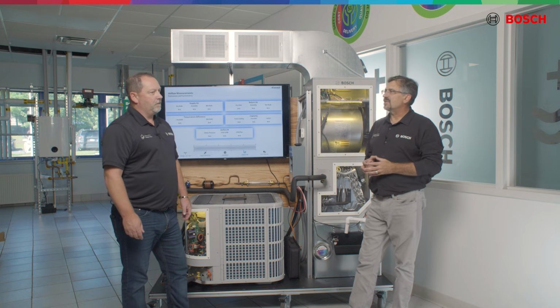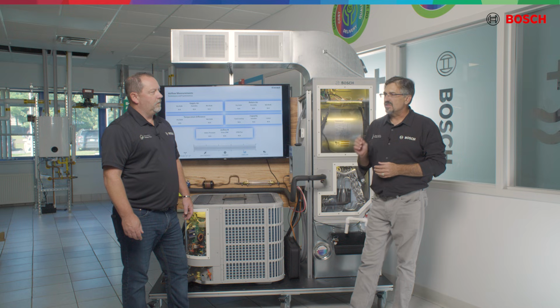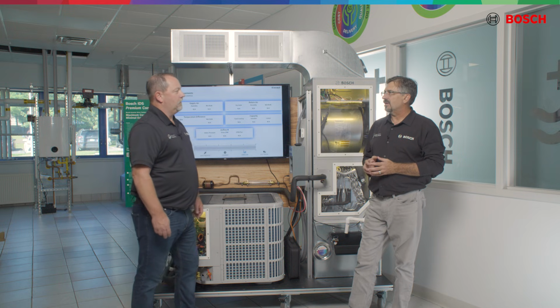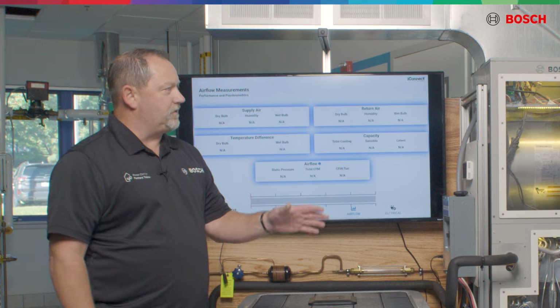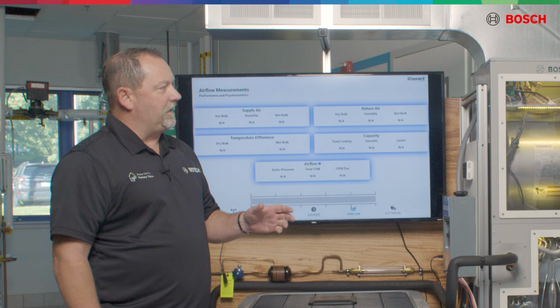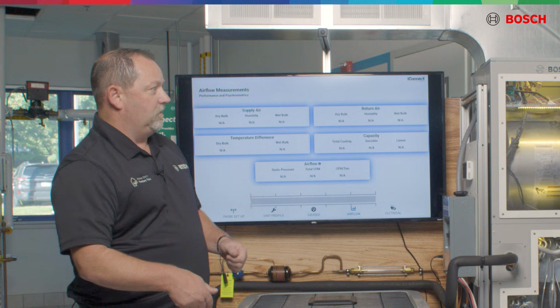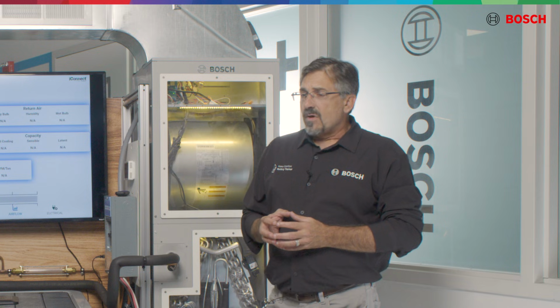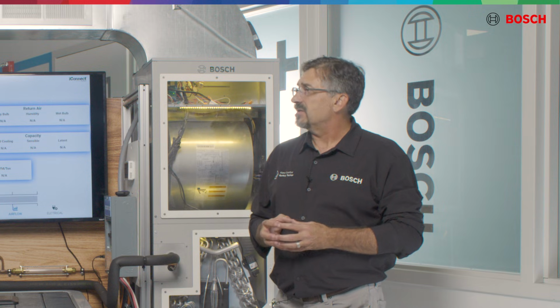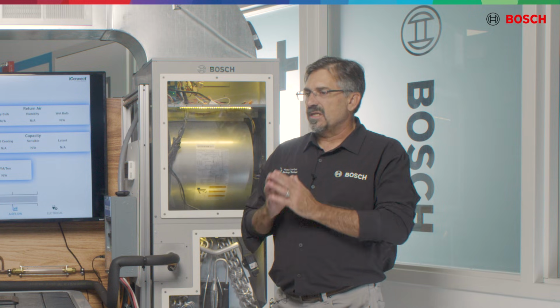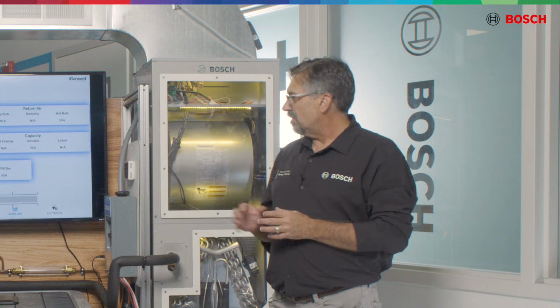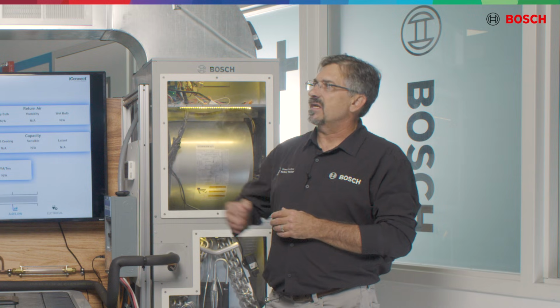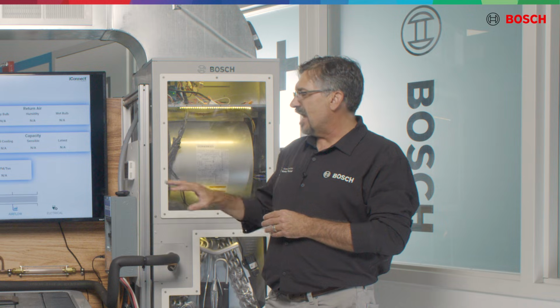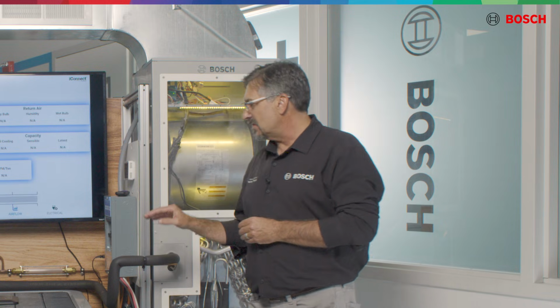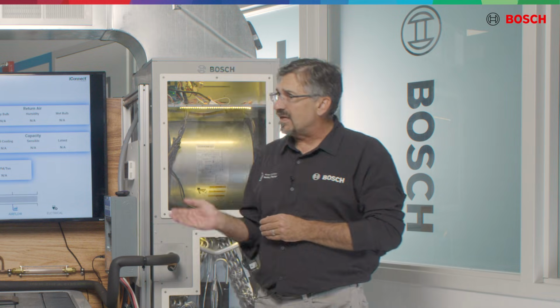The airflow moving across the evaporator coil in the cooling mode is the most essential aspect of this system operating correctly. So less airflow means less heat transfer. Less heat transfer means the compressor ramps down, thus reducing BTU output. Airflow is so critical, we don't realize, but it's been a problem in our industry the whole entire time as long as we've been installing equipment. The reason it's a problem now is the airflow is so critical of this system modulating up and down. Like I was saying about that fixed speed compressor, it did not know what was going on inside. This system now knows what's going on inside and it's going to modulate up and down.